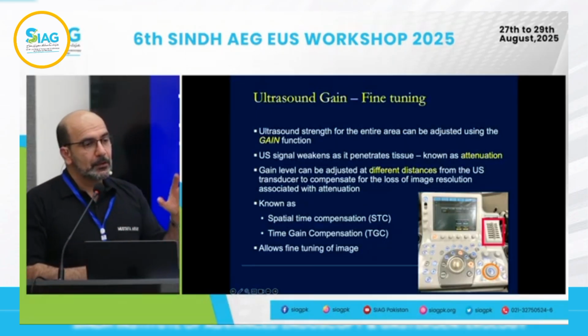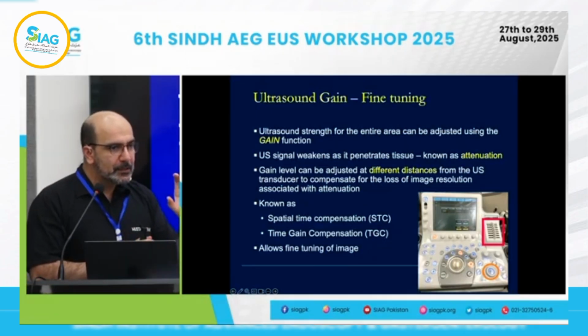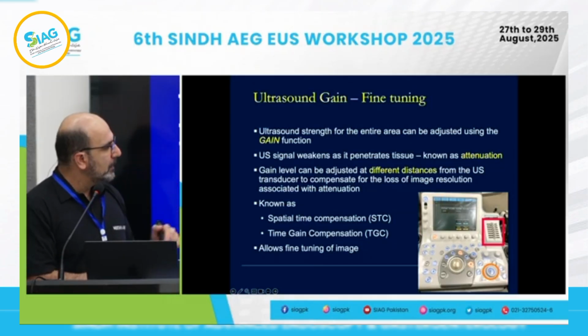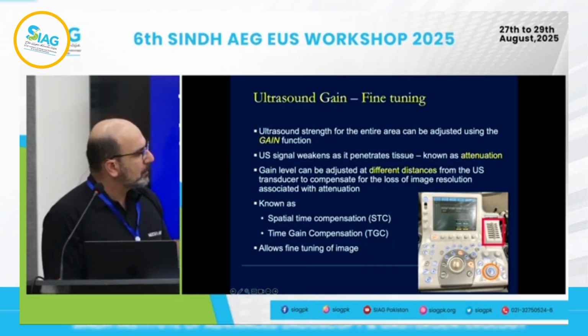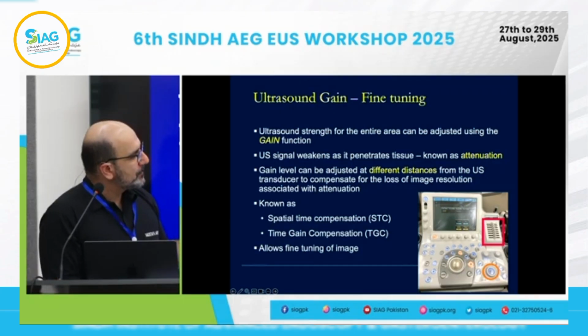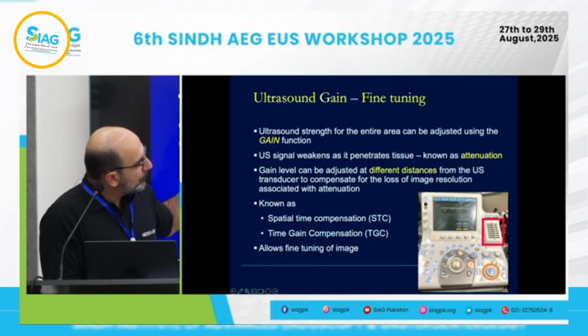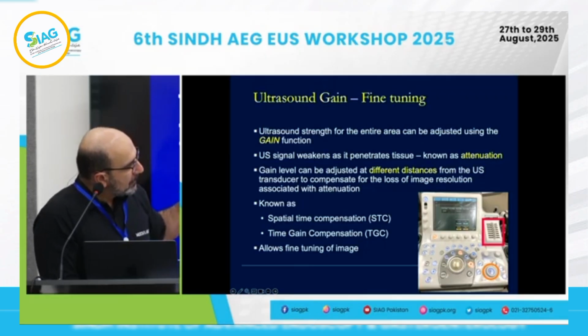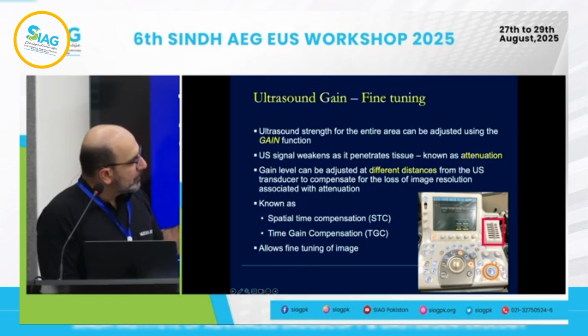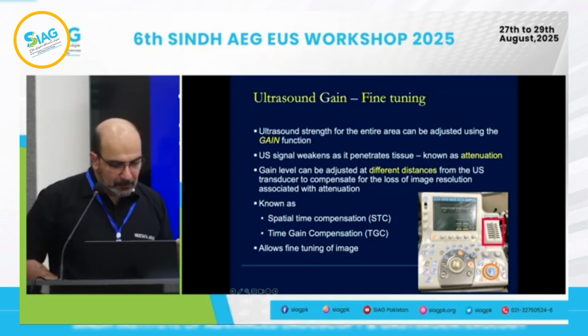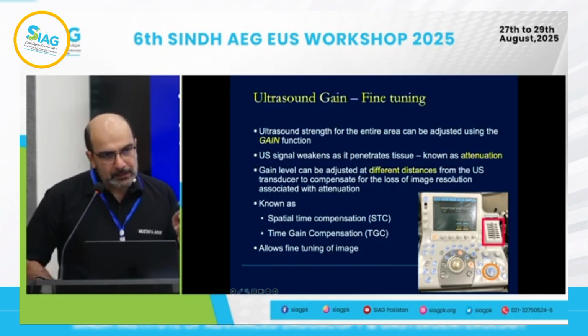Think of it this way: you can adjust your main focus, and then you can do fine tuning of your focus. Depending on the machine, it's known as STC, spatial time compensation, or time gain compensation. Along the depth of your image, at different levels of depth, you can adjust your gain. You usually have a slight slant to the right, but if one area seems like there's a problem, you can adjust it based on the depth of your image on the screen. We'll show you that when we do this. But the point is that you can do main focus and then fine focus to get your image.